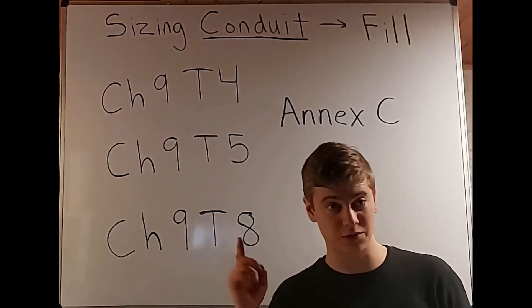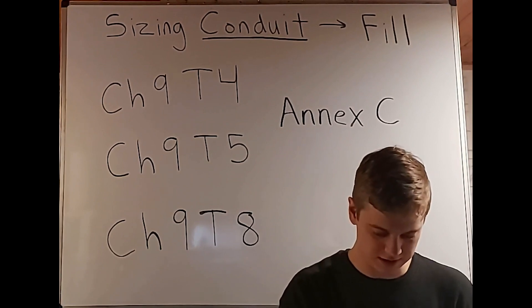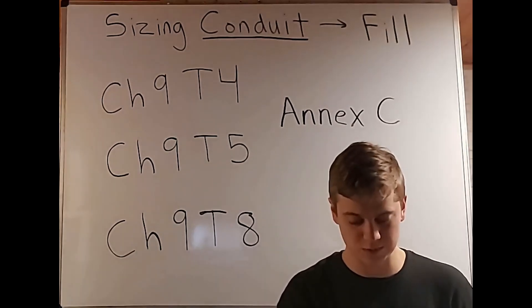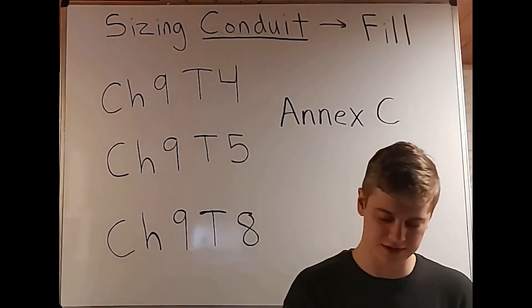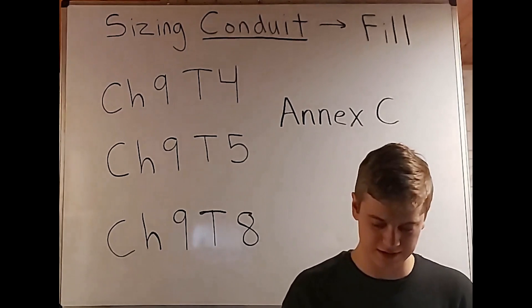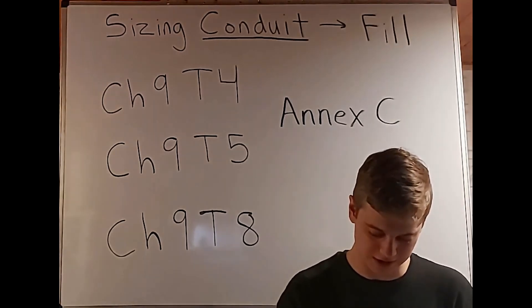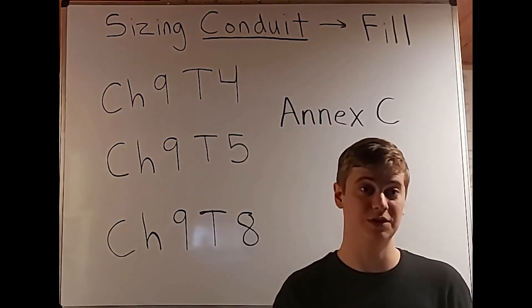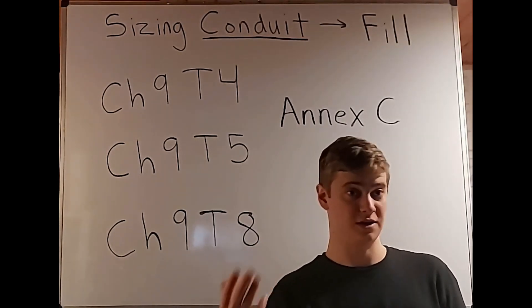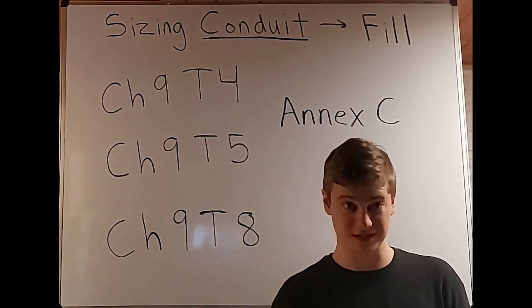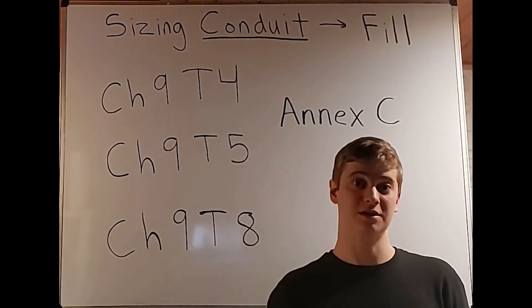Table 5 goes on for a bit, and then we get to Table 8, which is another key table. We'll see our size in AWG, then millimeters squared, and more importantly, circular mils — this is where we size circular mils from our wire. For bare copper, we look at the area column under 'overall area,' where we see square inches. If we're doing a conduit fill problem with bare copper conductors, that's where we find their size in square inches.